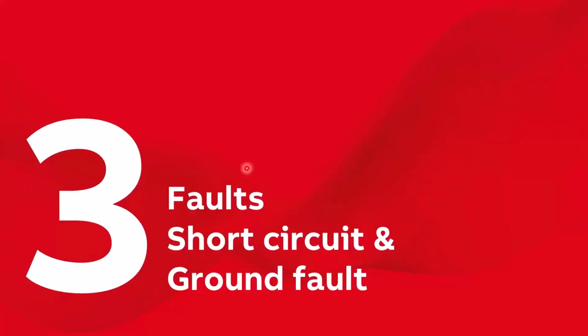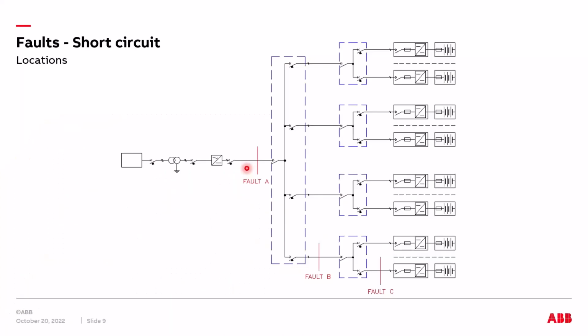So let's talk about faults now that can occur in our DC infrastructure. If we talk about DC short circuit, where are the typical fault locations? We can have basically the fault A in this section between the main AC-DC converter and the DC recombiner. The fault B, a short circuit that can occur between the DC recombiner and one or more DC combiners, and a fault C, which usually occurs between the DC combiner and the DC fast charger.